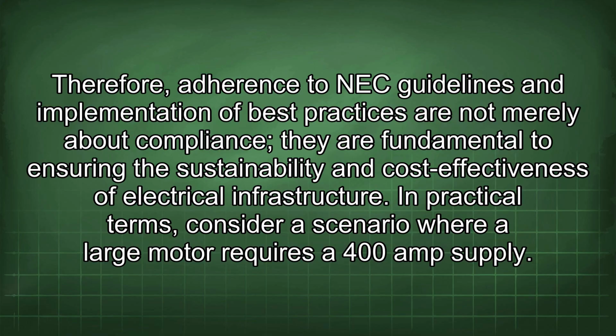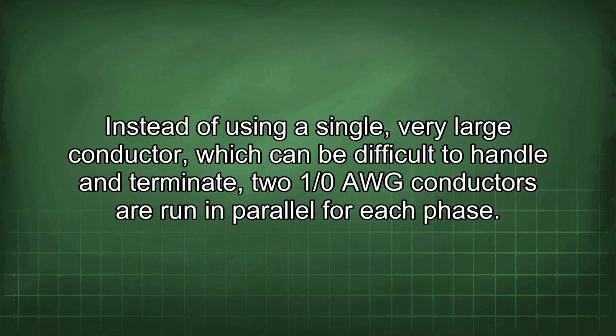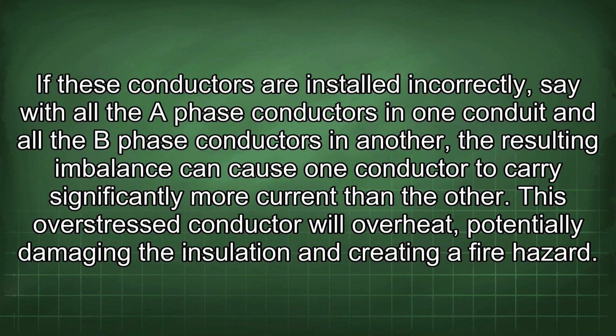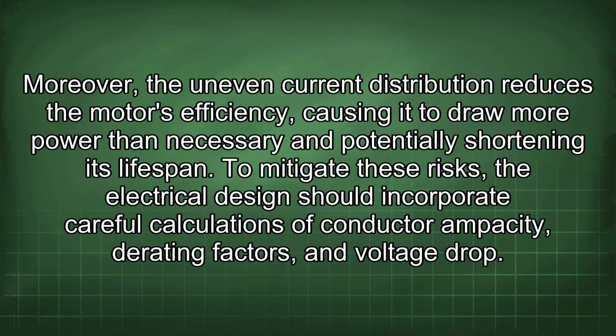In practical terms, consider a scenario where a large motor requires a 400 amp supply. Instead of using a single, very large conductor, which can be difficult to handle and terminate, 2 1/0 AWG conductors are run in parallel for each phase. If these conductors are installed incorrectly, say with all the A-phase conductors in one conduit and all the B-phase conductors in another, the resulting imbalance can cause one conductor to carry significantly more current than the other. This overstressed conductor will overheat, potentially damaging the insulation and creating a fire hazard. Moreover, the uneven current distribution reduces the motor's efficiency, causing it to draw more power than necessary and potentially shortening its lifespan.